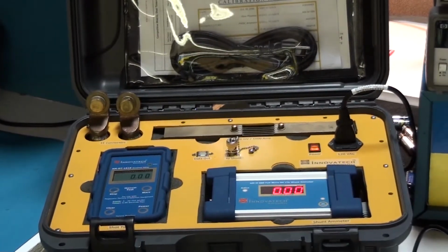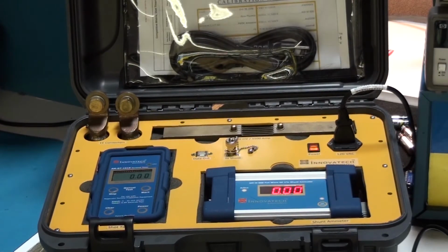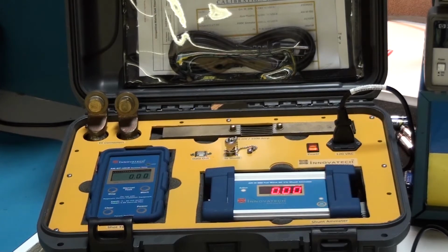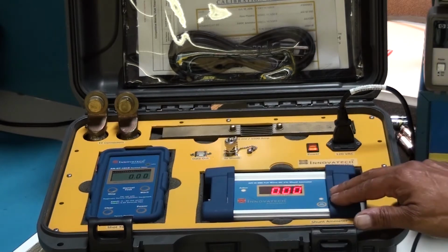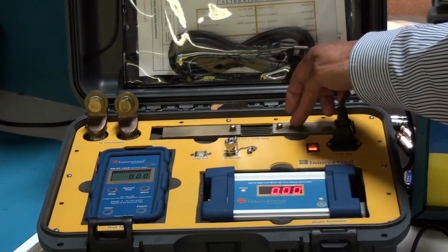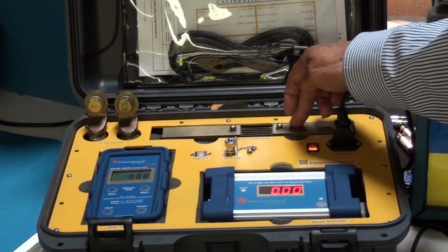And here, this unit is a 1% standard shunt ammeter, full wave DC, means averaging. It was calibrated for full wave DC at 50 millivolts to 1500 amp shunt. And that's what this ammeter is calibrated for. Here's your 50 millivolt, 1500 amp shunt.